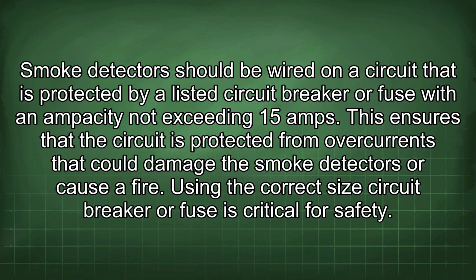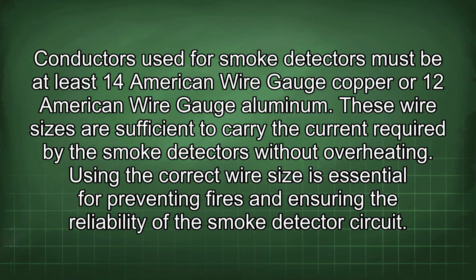Smoke detectors should be wired on a circuit that is protected by a listed circuit breaker or fuse with an ampacity not exceeding 15 amps. This ensures that the circuit is protected from overcurrents that could damage the smoke detectors or cause a fire. Using the correct size circuit breaker or fuse is critical for safety. Conductors used for smoke detectors must be at least 14 American wire gauge copper or 12 American wire gauge aluminum. These wire sizes are sufficient to carry the current required by the smoke detectors without overheating. Using the correct wire size is essential for preventing fires and ensuring the reliability of the smoke detector circuit.